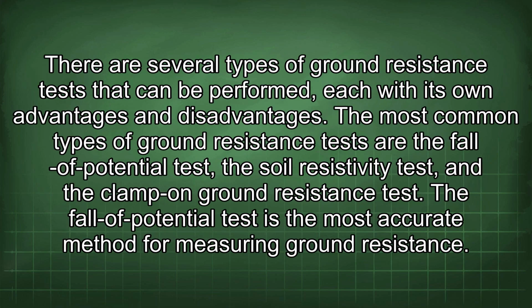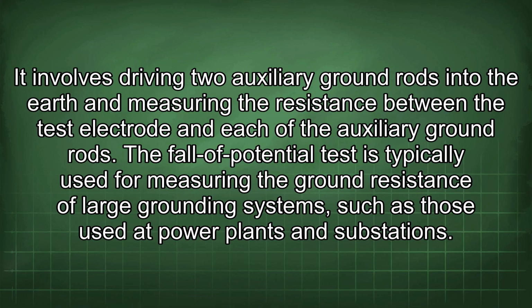There are several types of ground resistance tests that can be performed, each with its own advantages and disadvantages. The most common types of ground resistance tests are the fall-of-potential test, the soil resistivity test, and the clamp-on ground resistance test. The fall-of-potential test is the most accurate method for measuring ground resistance. It involves driving 2 auxiliary ground rods into the earth and measuring the resistance between the test electrode and each of the auxiliary ground rods. The fall-of-potential test is typically used for measuring the ground resistance of large grounding systems, such as those used at power plants and substations.